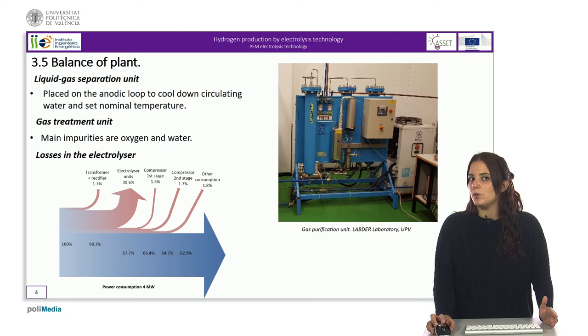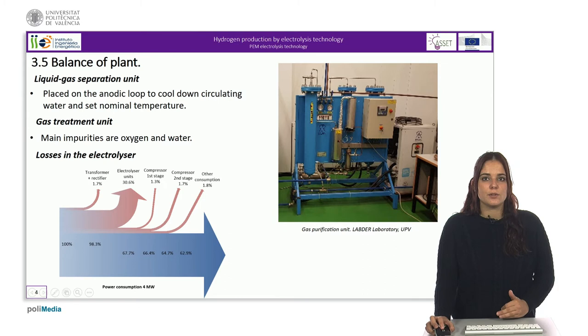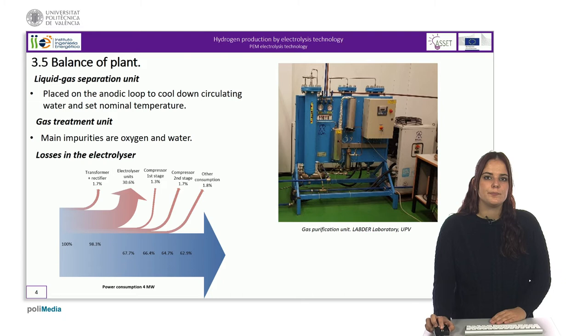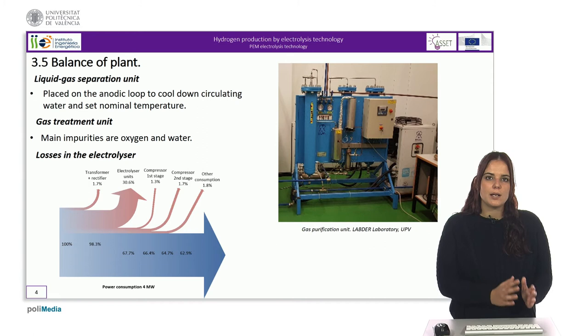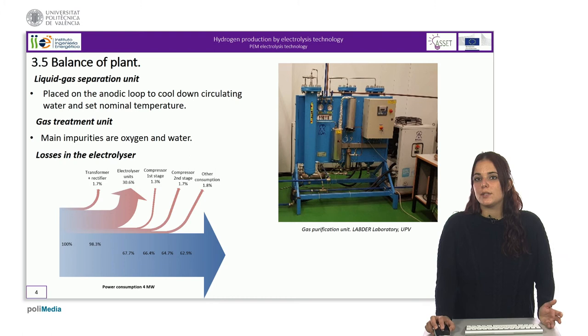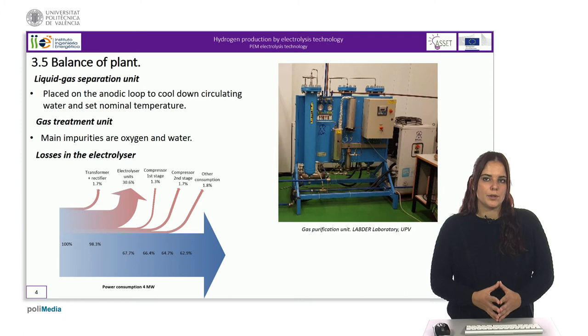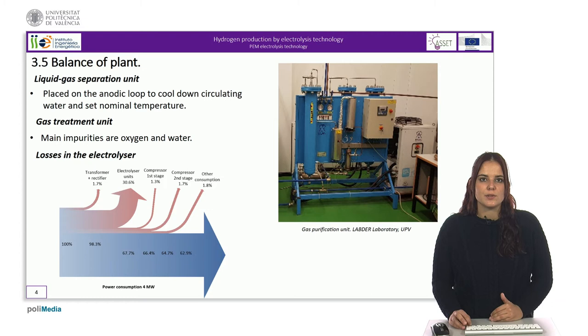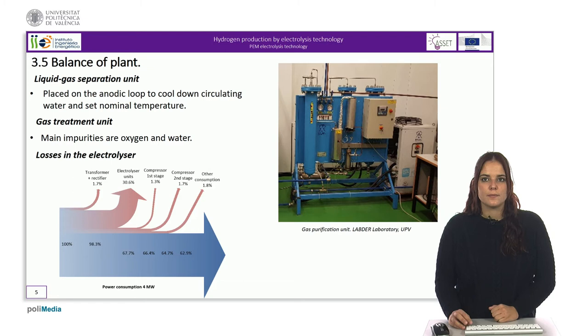Here we have in detail the liquid-gas separation unit and the purification unit. The liquid-gas separation unit is placed on the anodic loop, as well as a heat exchanger to cool down circulating water and set the nominal operating temperature. These units are placed at the exit of both the cathode and the anode. The electroosmosis flow of water collected on the cathode side is transferred back to the anode at regular time intervals or sent back to the water treatment unit. For the gas treatment unit, hydrogen purification is usually included in the PEM water electrolysis plant; the level of gas purity is a function of the application and customer specification. The main impurities are oxygen and water. Oxygen can be eliminated by passive catalytic recombination, while water can be eliminated by using a chiller of appropriate capacity and/or by temperature swing adsorption.